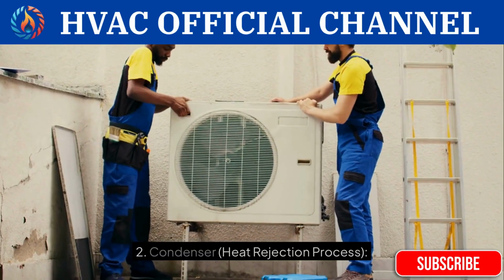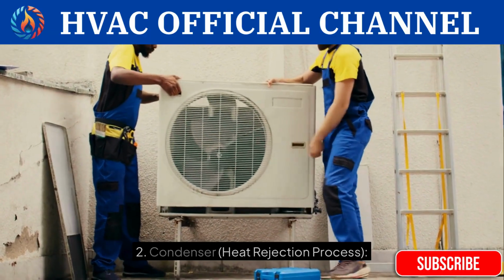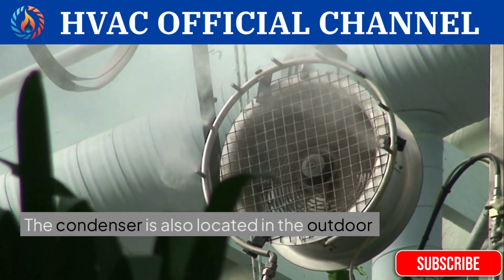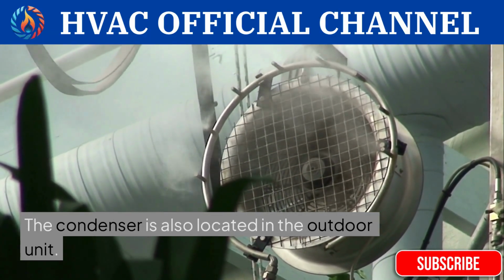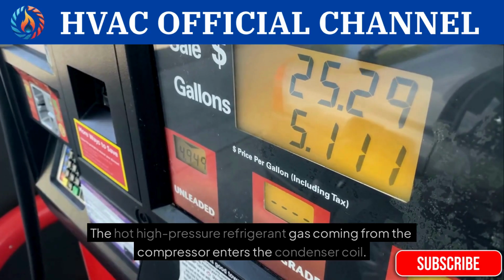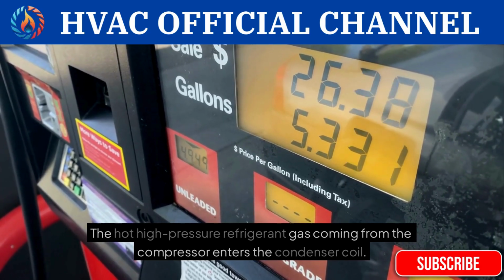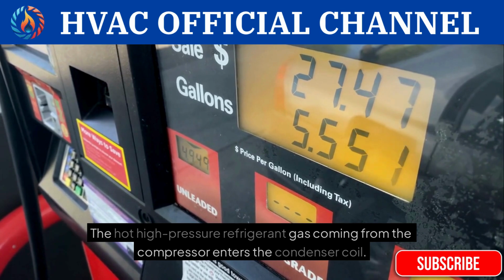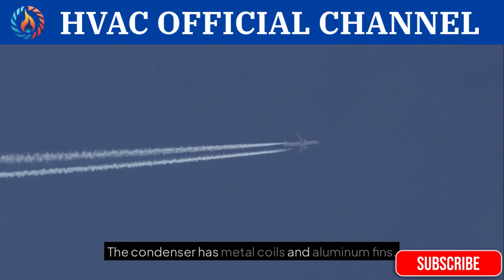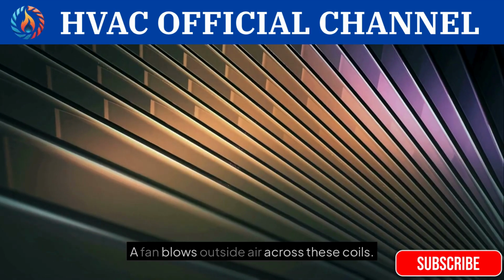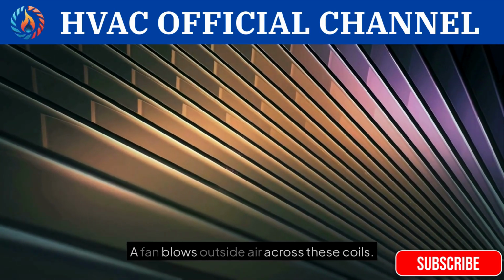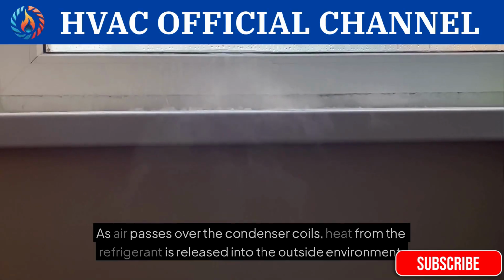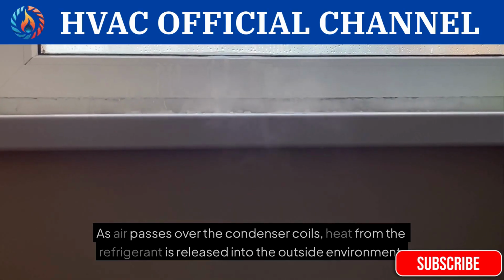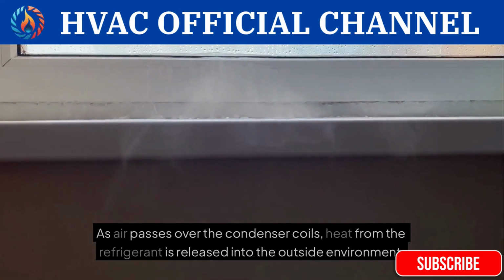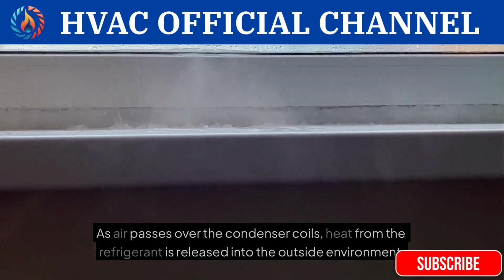2. Condenser, heat rejection process. The condenser is also located in the outdoor unit. The hot high-pressure refrigerant gas coming from the compressor enters the condenser coil. The condenser has metal coils and aluminium fins. A fan blows outside air across these coils. As air passes over the condenser coils, heat from the refrigerant is released into the outside environment.